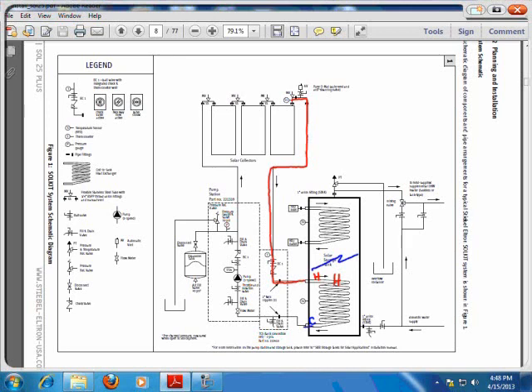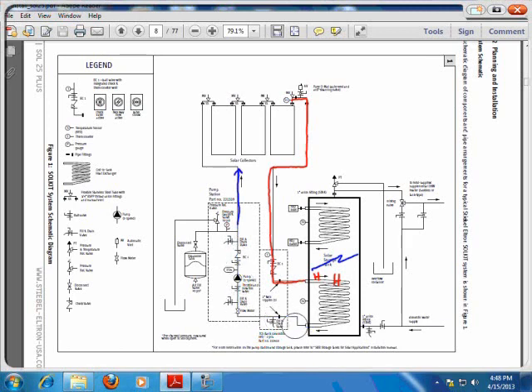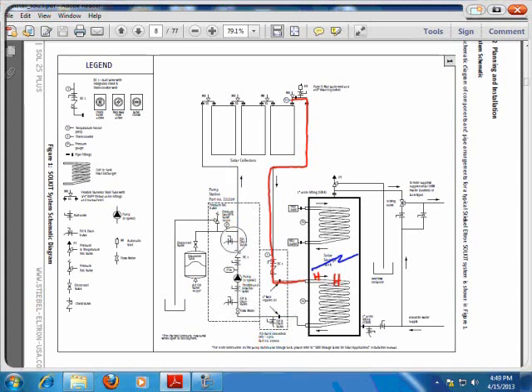And the reason we want it to be a little bit colder is because this water is still screaming hot. But compared to the water coming in from the solar collectors up on the roof, it's going to be markedly cooler. So we always put our pump, the expansion tank, our valves, our fills, all this stuff right here, always is going to be on the cold side or colder side as it's called.